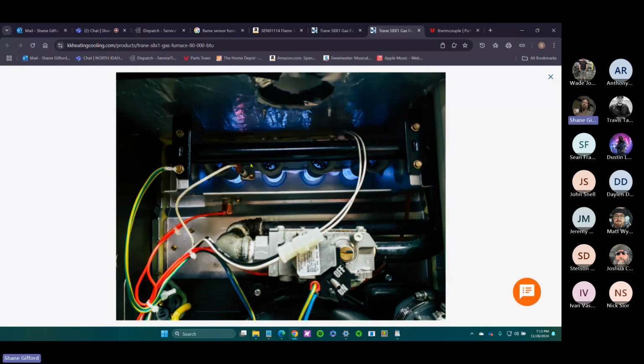So once you're up and running and you're burning, you're rectifying flame off your thermocouple, and it's going back to your board and it's saying, here's the volts that I'm reporting. And then that will right then and there tell the board either run or kill everything. If you've got proper millivolts, then you're going to continue to run and you're good. You've completed all of your safety checks. Last but not least, your blower kicks on and then you're off and running. These are all wired in series, or they report back to a specific spot on the board. But they make it so that if any one of these things fails, it kills the system. And that's the same for pretty much any hot side appliance.